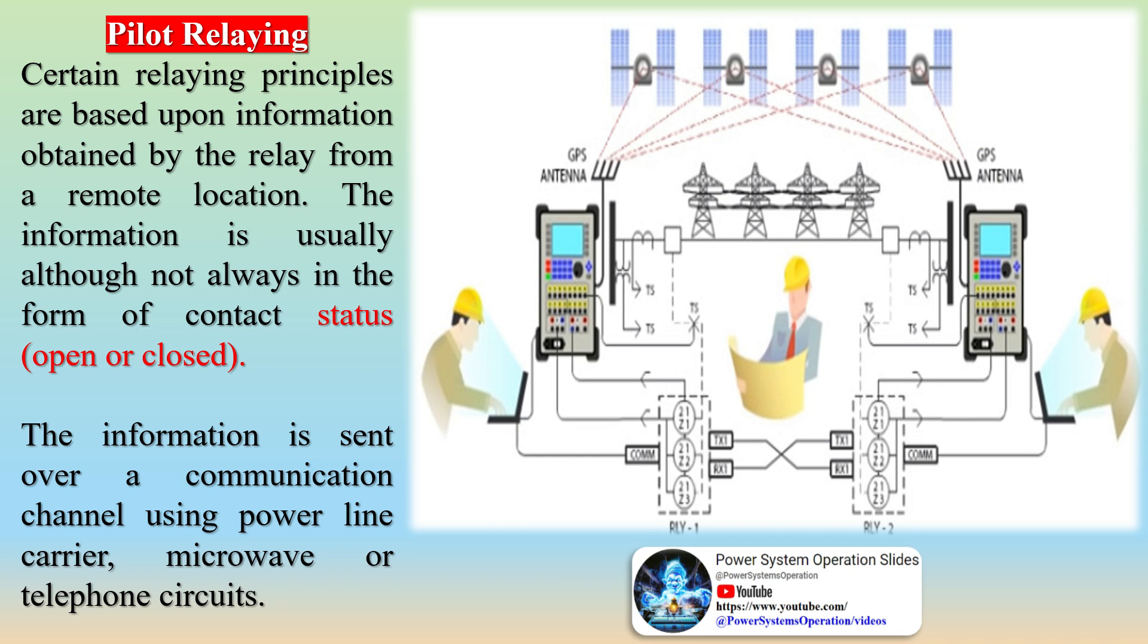Pilot relaying. Certain relaying principles are based upon information obtained by the relay from a remote location. The information is usually, although not always, in the form of contact status, open or closed. The information is sent over a communication channel using power line carrier, microwave, or telephone circuits.